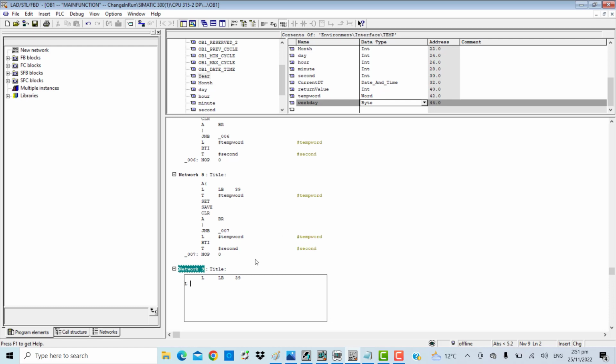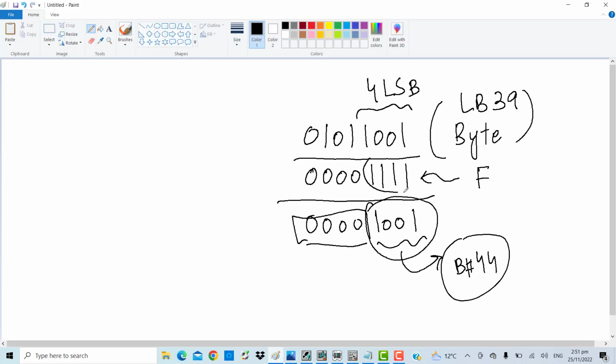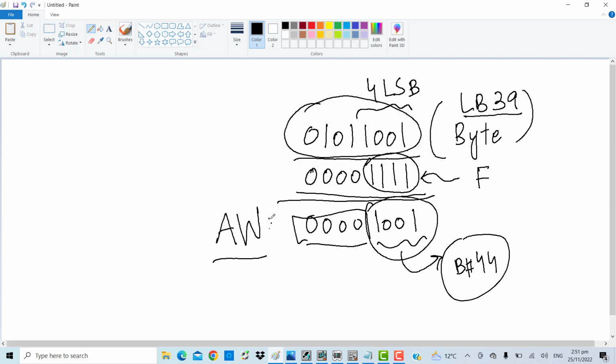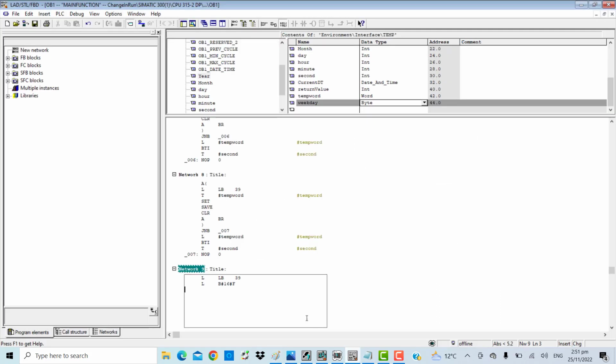I'm going to load another byte whose value is F. First I loaded this byte LB39, then I loaded F, and then I'm going to do the AND word operation, because I can't simply apply the AND that I use for bit operations. I have to use the instruction A word. And once that AND operation is done, I'm going to transfer the result to the byte with the name of weekday.